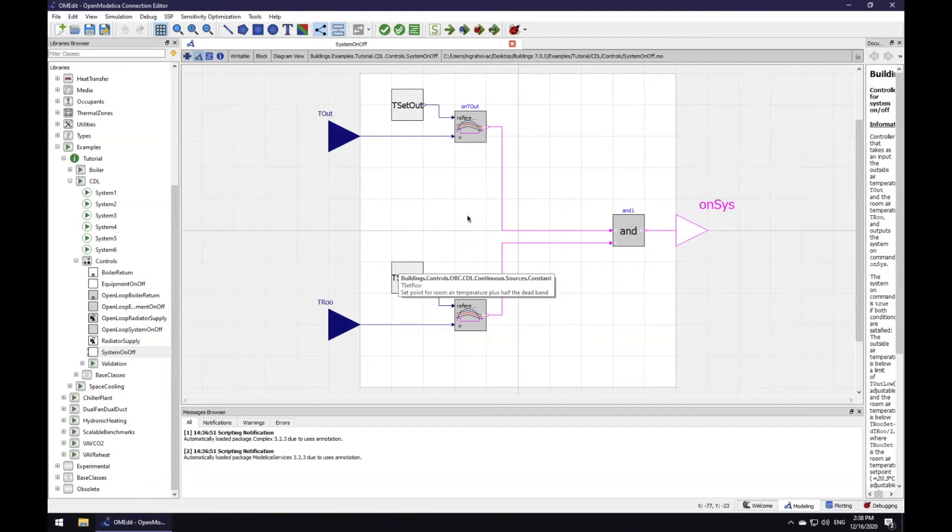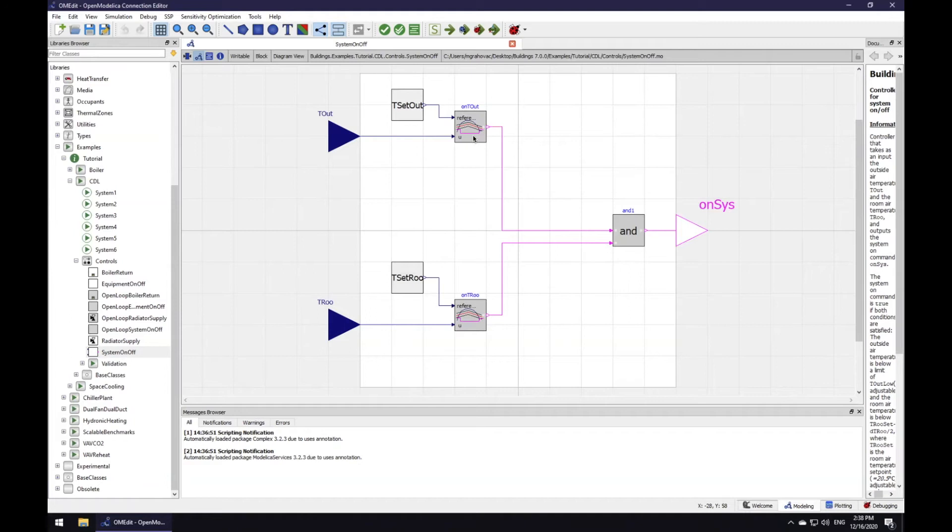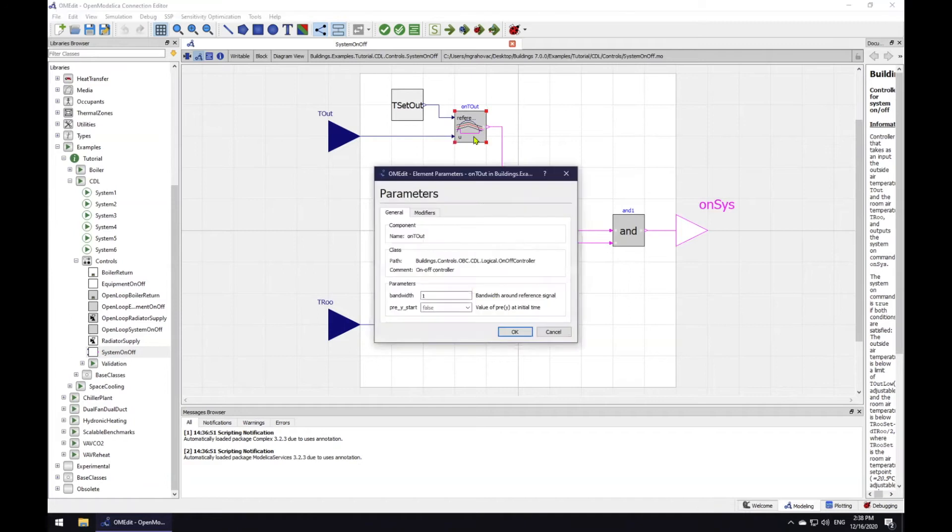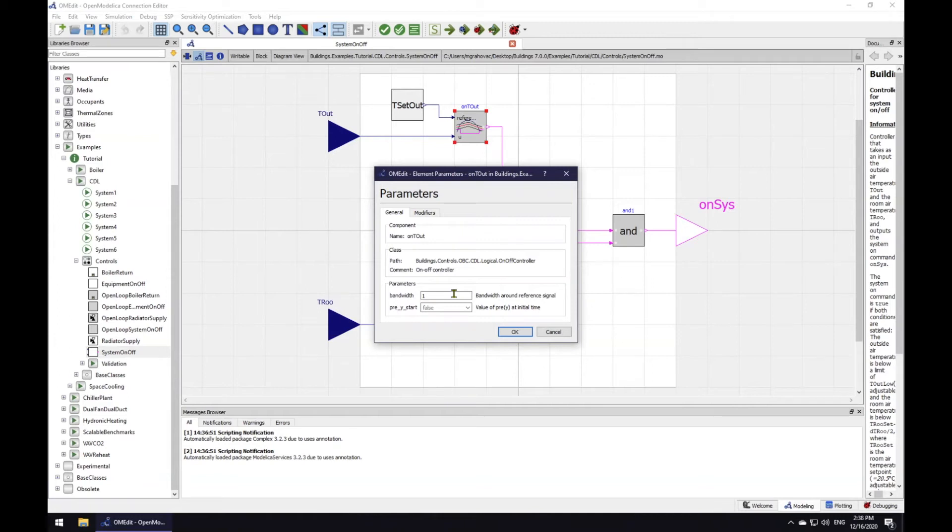Each of the constant temperature signals is being compared with the corresponding sensor output signal using an on-off switch that contains an inbuilt hysteresis. This hysteresis enables us to avoid short cycling as it uses an offset between the value which causes the device to turn on if it was previously off and the value which causes the device to turn off if it was previously on.